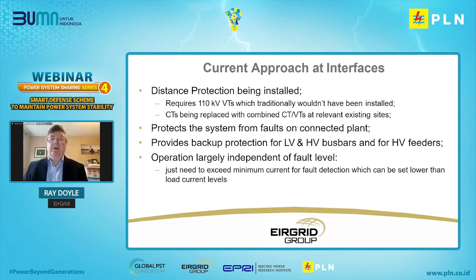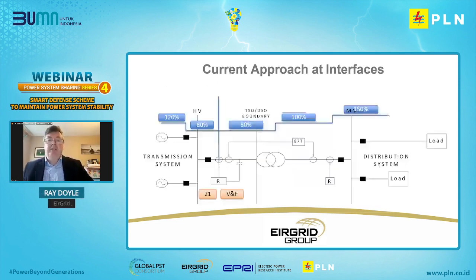Okay, so what we're doing now at new interfaces, and we're also retrofitting this to existing interfaces, is putting distance protection on the HV side of the transformer, which requires 110 kV VTs, which typically would not have been installed. Where we have CTs only, we're replacing them with combined CT-VT units. This is used to protect the system from faults on the connected plant, and it also provides backup protection for LV and HV busbars and for HV feeders. The good thing about this is that the operation is largely independent of system fault level. We just need to exceed a minimum current for fault detection, which can be set lower than load current levels, which was not the case previously. Next slide, please.